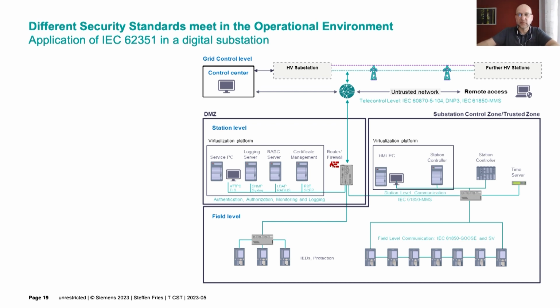So there is a whole ring of protection devices which communicate with each other, exchanging values like current, voltage, and phase angle. Depending on the evaluation of those values, a trip might be issued to avoid a short in the wiring, or to prevent a short from affecting the rest of the plant.